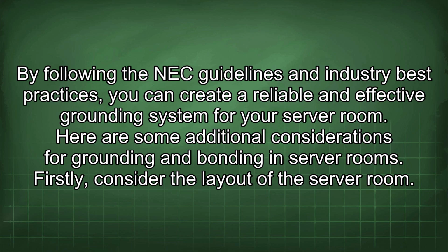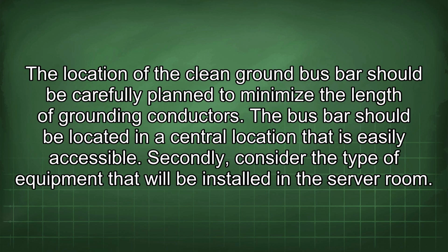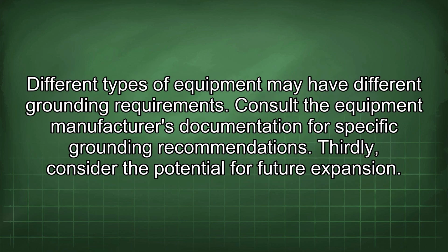Firstly, consider the layout of the server room. The location of the clean ground bus bar should be carefully planned to minimize the length of grounding conductors. The bus bar should be located in a central location that is easily accessible. Secondly, consider the type of equipment that will be installed in the server room. Different types of equipment may have different grounding requirements. Consult the equipment manufacturer's documentation for specific grounding recommendations.